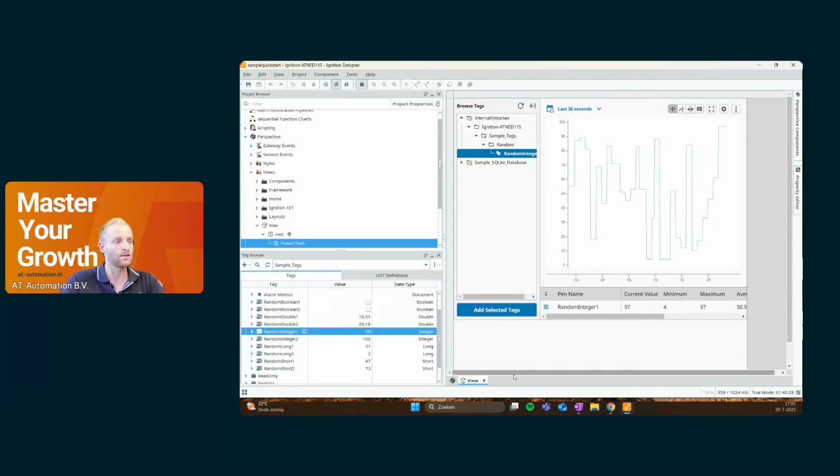However, it's more optimized, and I have to believe Inductive Automation is way more powerful. The difference is that with the old historian, whenever you were looking for, for instance, a maximum, minimum, or average of a tag over a certain time period, Ignition would pull from the database all the data, and then Ignition would calculate the minimum and the maximum and so on. With the new Power Historian, Ignition will transfer the question to the time series database, which is way more optimized for doing calculations. So it's not moving that much data anymore. So that's the Power Historian, which is also included in the new version.